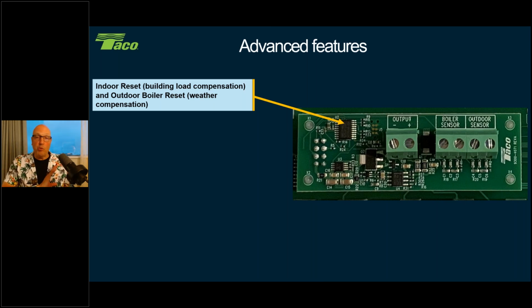Outdoor reset we've been doing for decades. All right, and it's a great way to add some energy savings to your system. But the way I look at outdoor reset is, if you want to take full advantage of outdoor reset, one, you should have one zone in the house. Two, the boiler should be exactly matched to the heat load. All right, which we know is not happening. So this way, indoor reset almost is, in my opinion, a little bit better, maybe a lot better than your weather compensation design, because it doesn't know what's going on in the house. It only knows what's going on outside. Okay, so a little bit different going on out there.